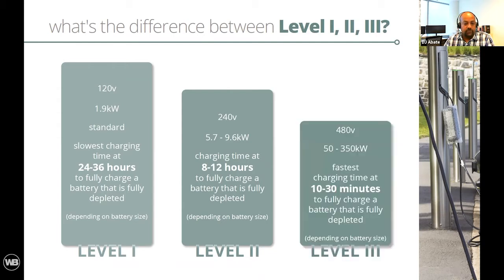Then there's level 3, also known as DC fast charging or supercharging, which as of today provides the fastest charge time. Level 3 requires a 480 volt connection, which gets converted from AC to DC current, allowing for much more rapid charging. Because of the high consumption rate and that AC-DC conversion, the only issue with level 3 is it requires additional electrical infrastructure, including switchboards, transformers, and power units located near the charging stations. Level 3 comes in different sizes, ranging from 50 kW all the way to 350 kW, and can provide a full charge in less than 30 minutes. Because of that fast charging capability, these chargers can generally be found in retail, office buildings, and some fleet applications where quick charge time is essential.